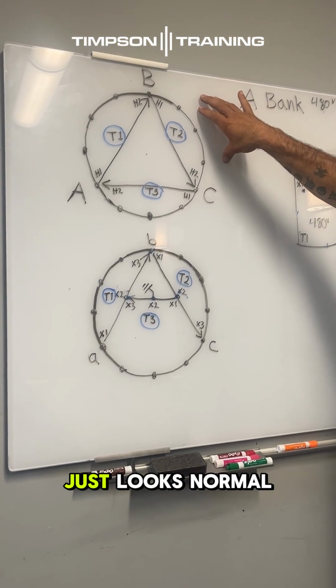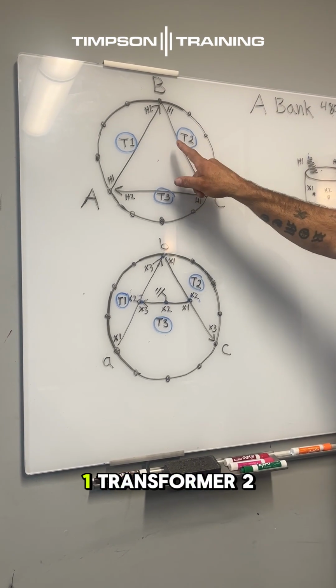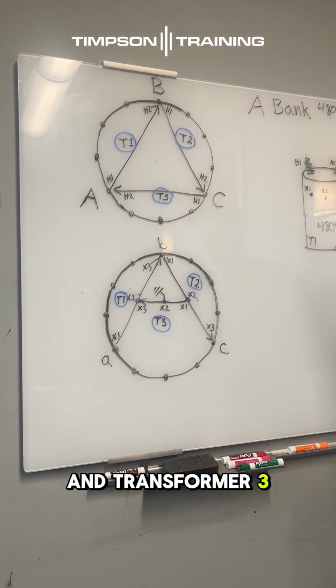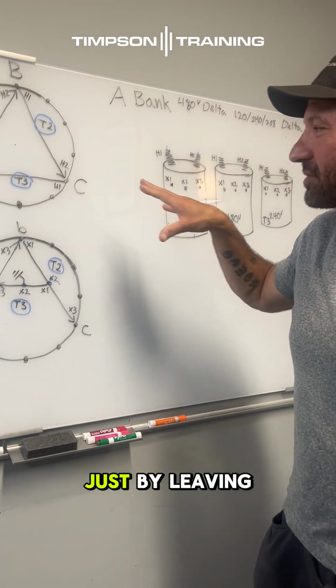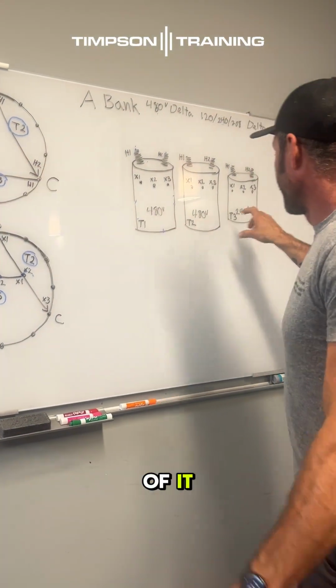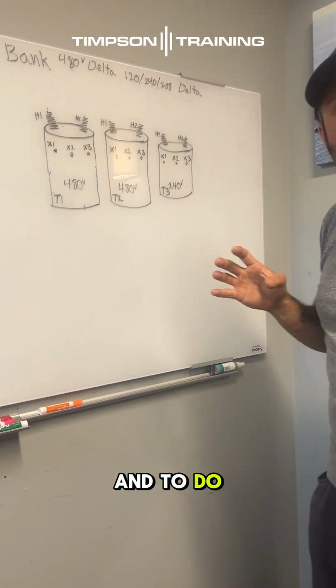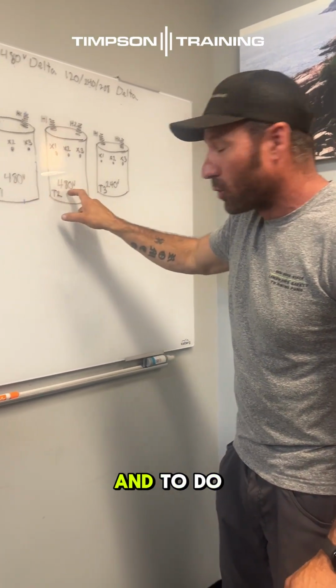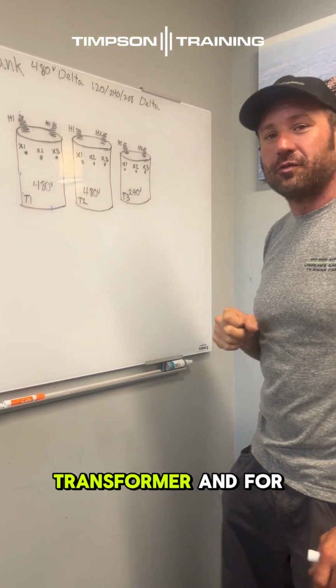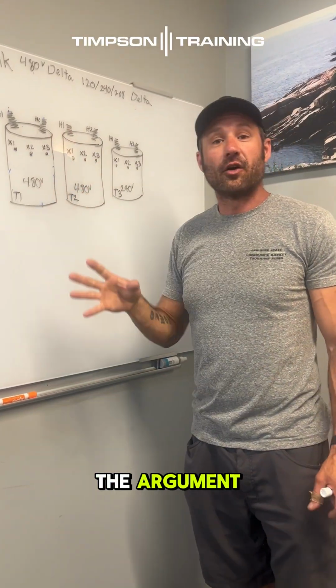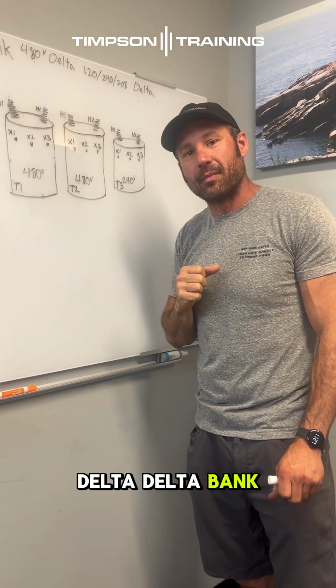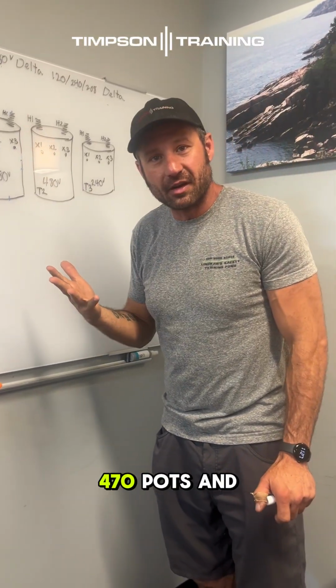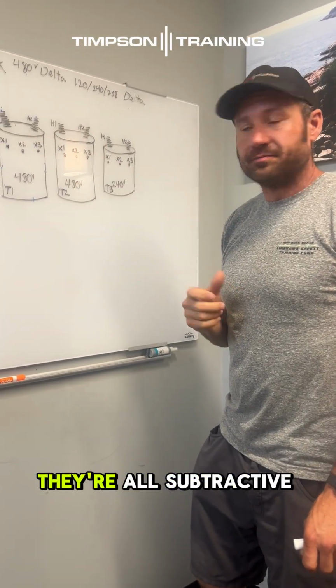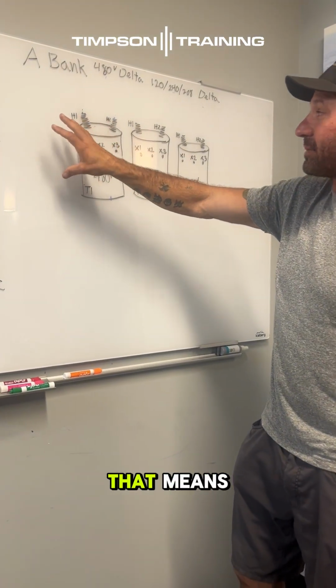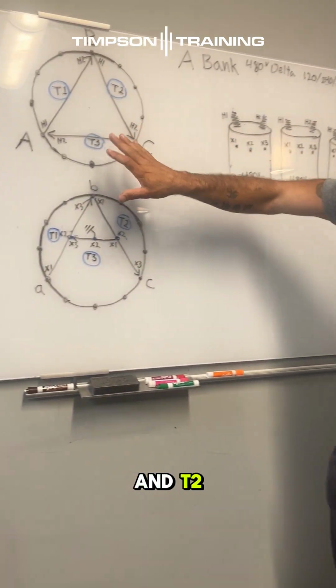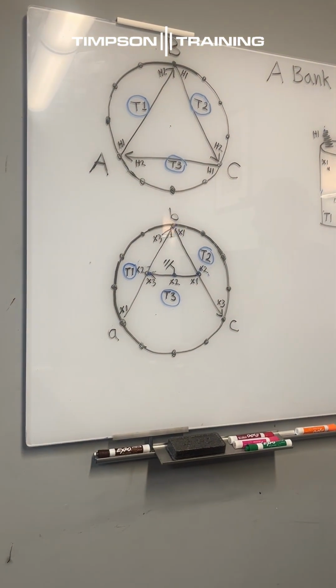Our primary vector just looks normal. You have transformer 1, transformer 2, and transformer 3. But we're going to start this out just by leaving transformer 3 out of it. So this will be transformer 3, and to do this bank, you need two 480 transformers and one 240 transformer. For the sake of argument, this is going to be a delta-delta bank. So we'll just say 12,470 primary, and they're all subtractive. Now, if we look at what that means, we're just going to start with T1 and T2, and pretend T3 doesn't exist.